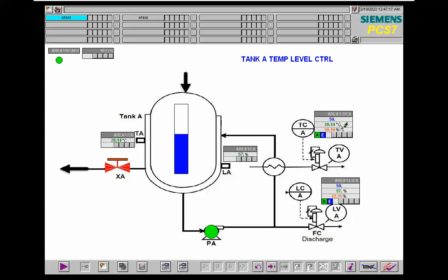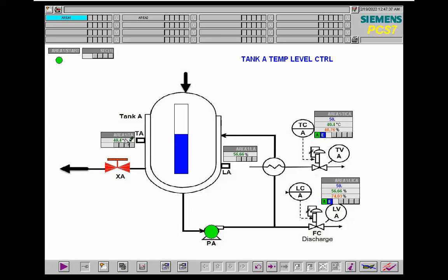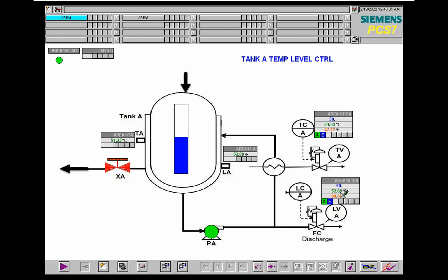The temperature should be maintained at 50. The current temperature is 30, so the valve should open. The mixture that is coming from here is getting warmed up, and the temperature of the tank will increase up to 50 centigrade. We have the inlet from here and now we have the outlet here. This is a very small valve in order to maintain the level, and we use this PID controller in order to maintain the level at 50%.